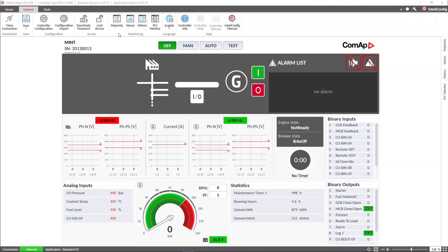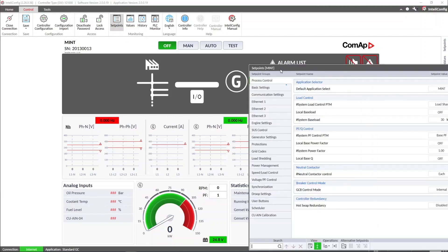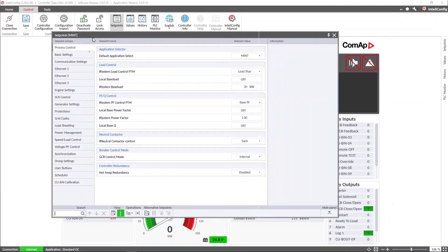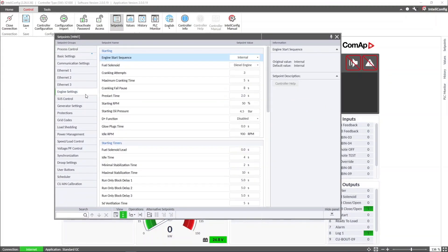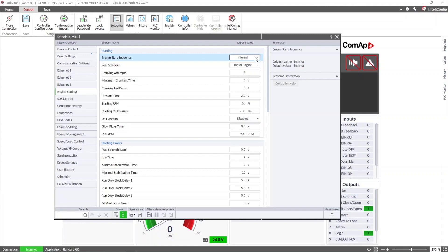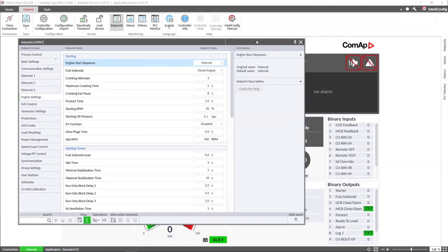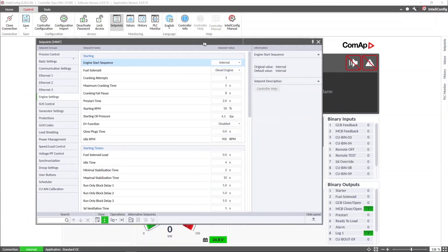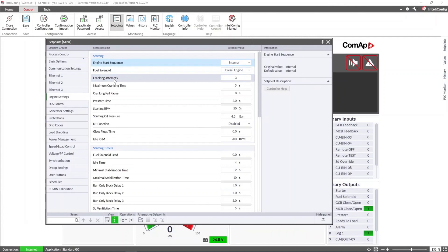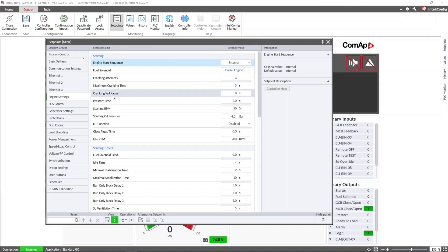By accessing the setpoints menu in the engine settings group, this type of controller lets us select if the engine start sequence will be handled by the intelligent controller or by the ECU or the engine control system. The option internal considers control and activation of starter and fuel solenoid outputs, and we can configure the maximum cranking time, the crank fail pause, and the cranking attempts.